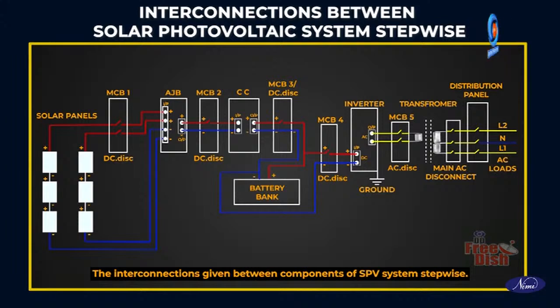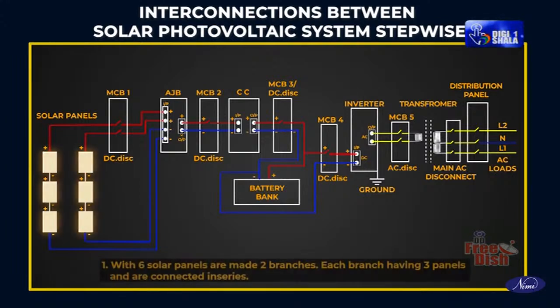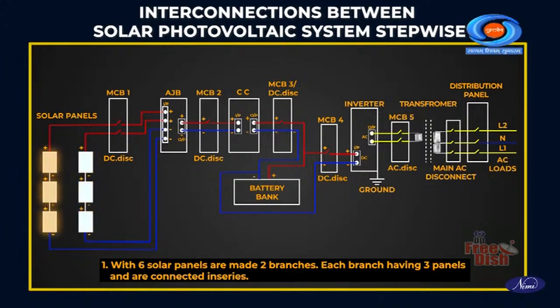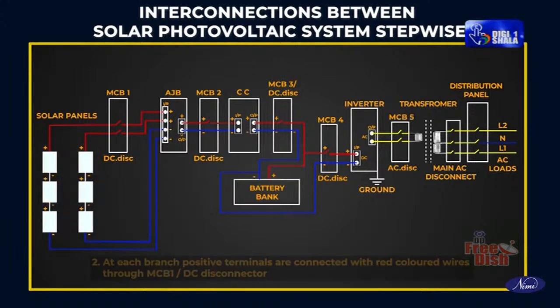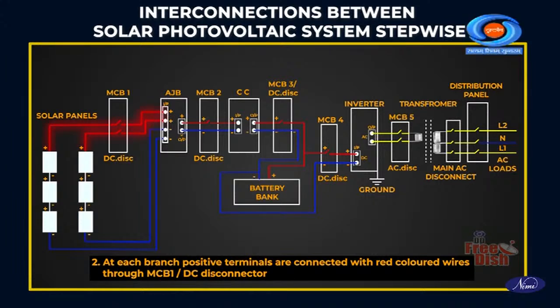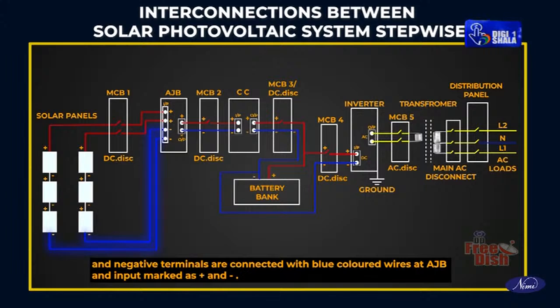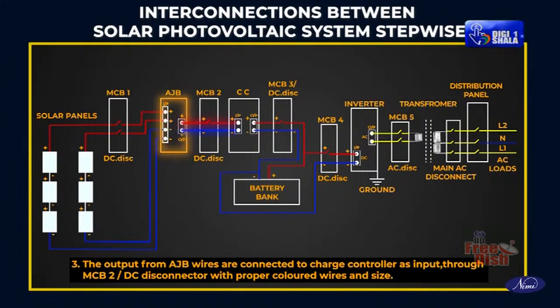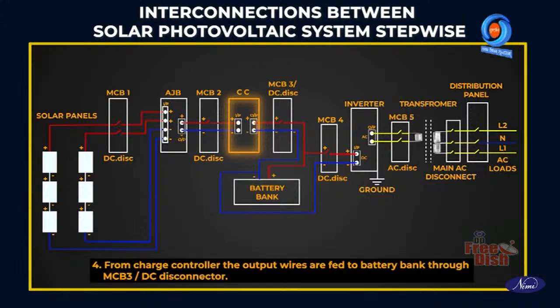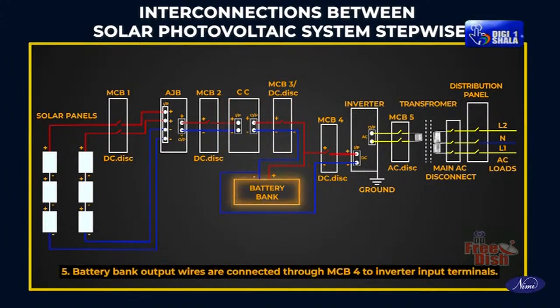The interconnections given between components of the solar photovoltaic system, stepwise. With 6 solar panels, 2 branches are made, each branch having 3 panels connected in series. At each branch, positive terminals are connected with red colored wires through MCB1 or DC disconnector, and negative terminals are connected with blue colored wires at the AJB, with inputs marked as plus and minus. The output from the AJB wires is connected to the charge controller as input through MCB2 or DC disconnector with proper colored wires and size. From the charge controller, the output wires are fed to the battery bank through MCB3 or DC disconnector. Battery bank output wires are connected through MCB4 to the inverter input terminals.